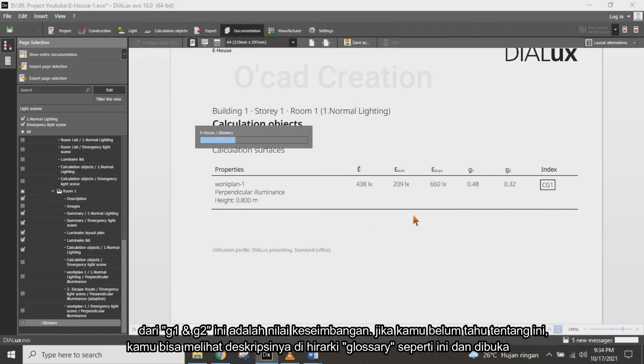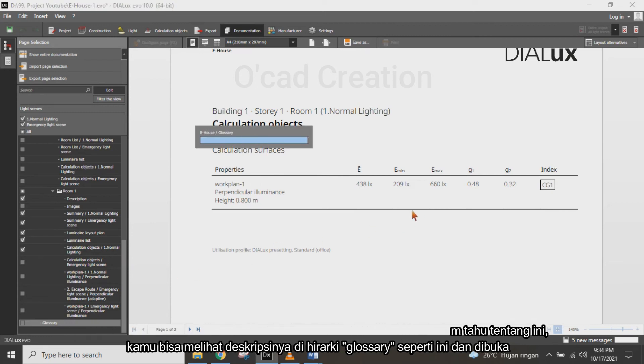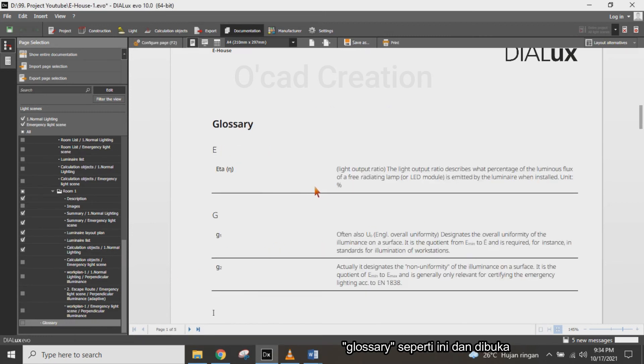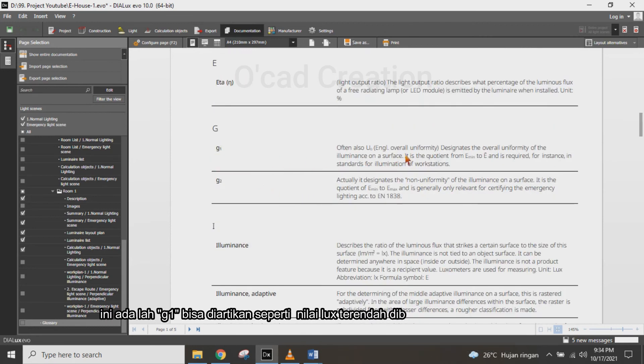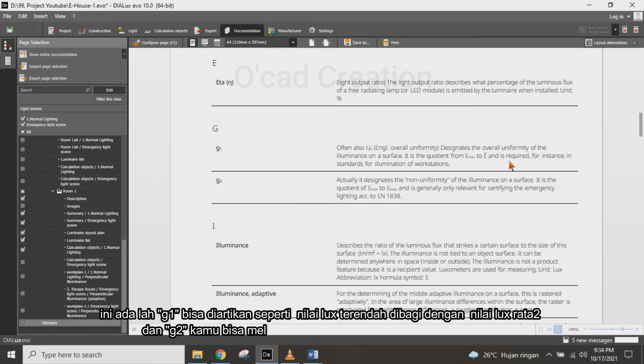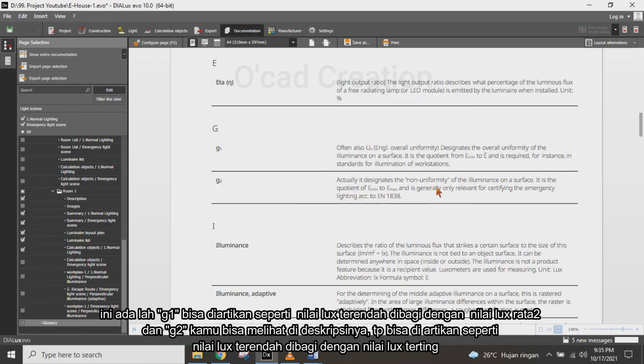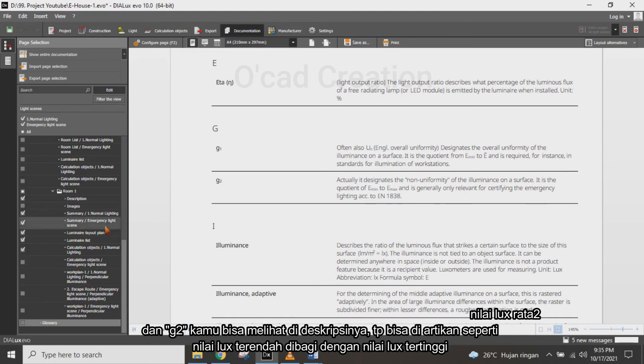There is also G1 and G2 uniformity values. If you don't know about G1 and G2, you can open the hierarchy to see the description. G1 is lux minimum divided by lux average, and G2 is lux minimum divided by lux maximum.